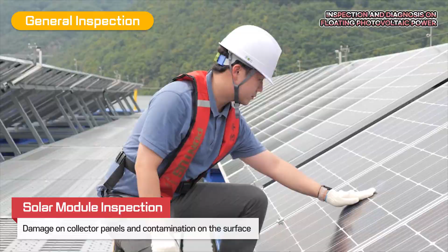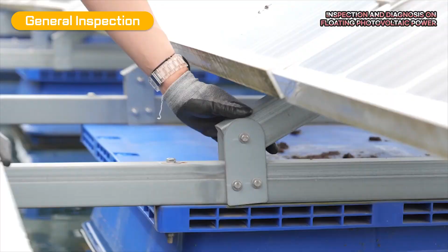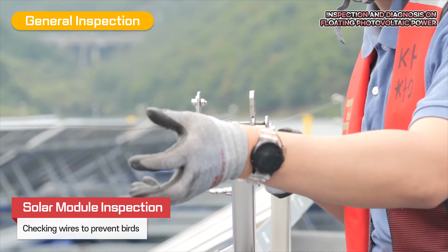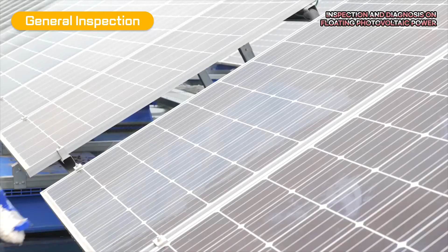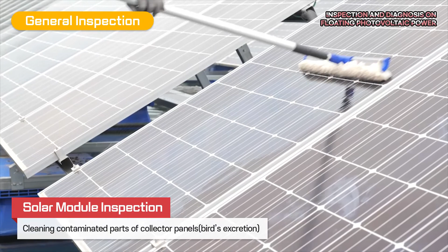First, in the general inspections, the inspection of solar modules is generally conducted through a visual check. The worker checks for damage or cracks on the module surface due to the external environment and checks for deterioration inside the module through an infrared thermal imaging camera in the suspected section. Moreover, wires are checked to prevent birds from interfering. If collector panels are contaminated by dust or bird excrement, they should be cleaned by mopping with water.